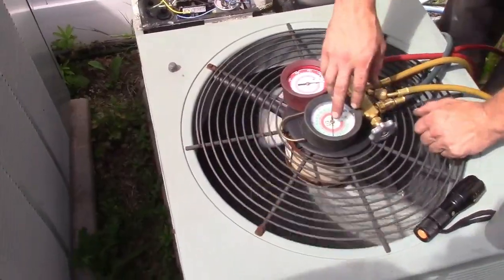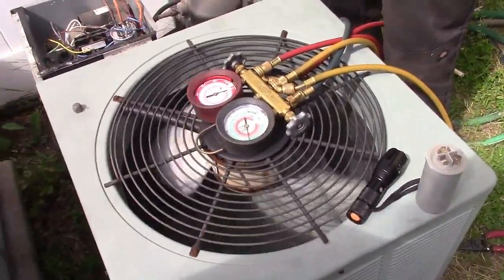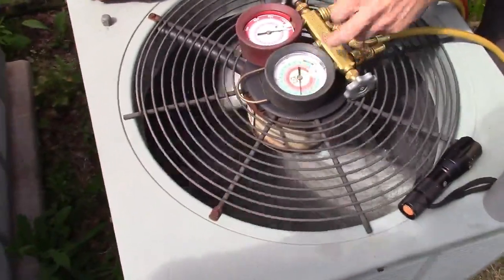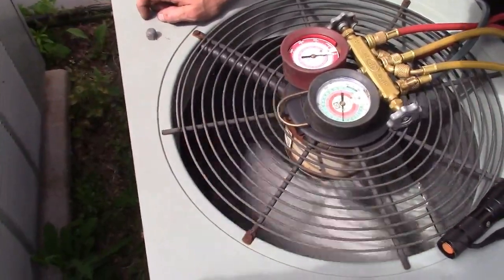You've got to give it a little while — this thing just turned on. But how hot is it inside? Probably 80-something. Because I got a 42-degree coil, which is good, especially for being 80 degrees inside.